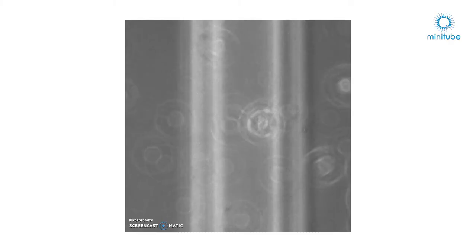When you are working with the e-flow system this is how the picture looks like when the condenser is at its top stop, the sample is well focused and the field diaphragm is closed. Again you have to center the condenser and then open the field diaphragm and adjust the light intensity.